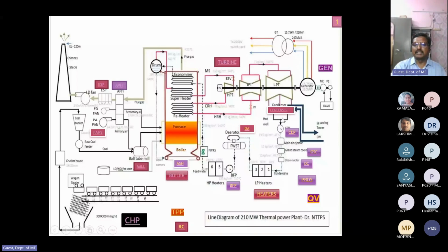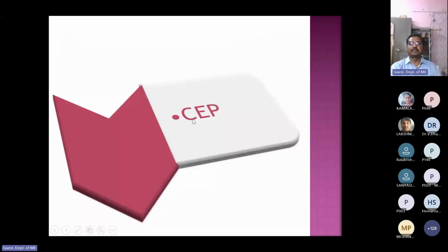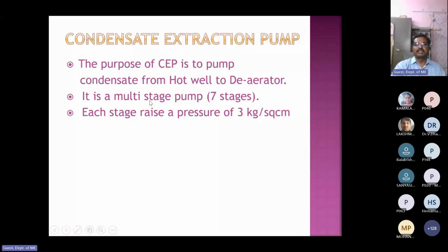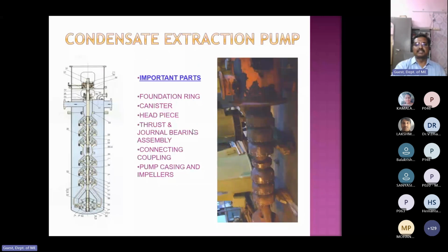From the hot well, with the help of the CEP, it supplies water up to the deaerator area. CEP means condensate extraction pump. The purpose is to pump condensate from the hot well to the deaerator. It is a multi-stage pump. In each stage, the rise of pressure is 3 kg per cm square, so the total is 7 stages, 21 kg per cm square. It will raise the pressure up to 7.